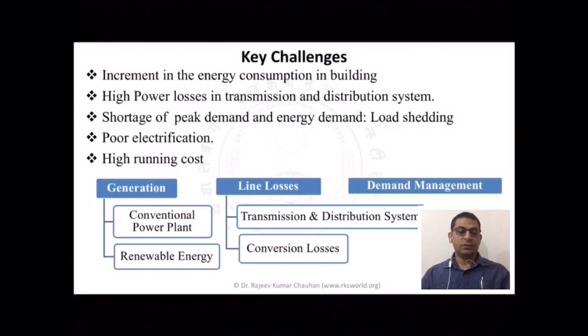Okay, the other thing is peak demand and energy demand. Whenever we design a system, we have to think about two parameters. One, the generating station should be designed with sufficient size to supply the rated or peak demand. It should be able to supply the peak demand, no matter if it occurs for a minute, an hour, or a day, but we have to design our power system to supply the load for the peak demand.